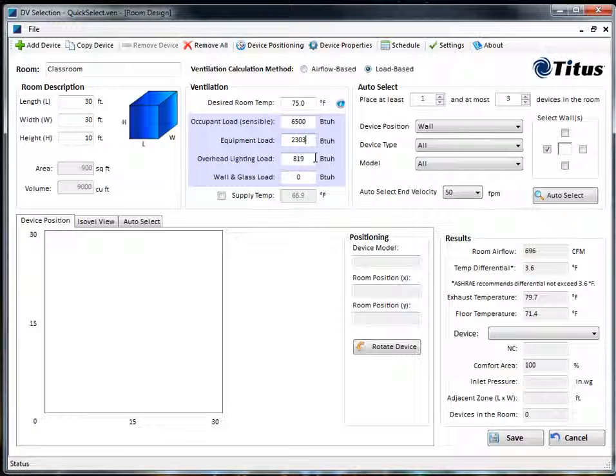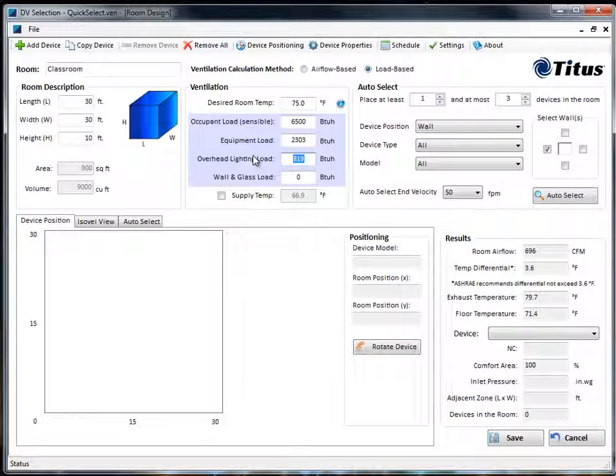For overhead lighting, let's say that we have two watts per square foot, so when you do the math on that you get 6,143 BTU.